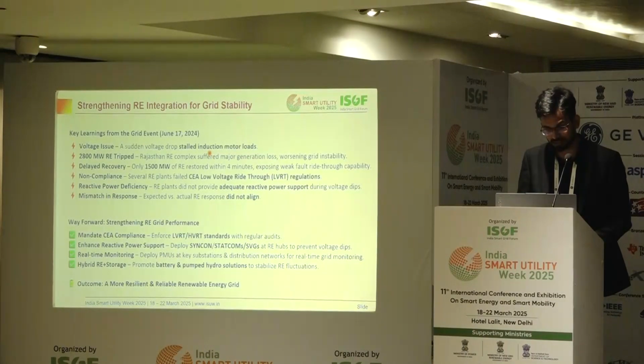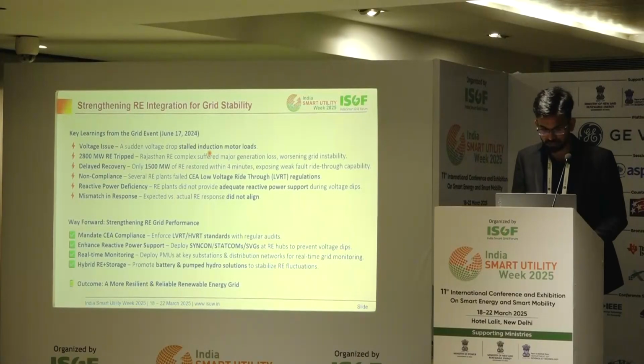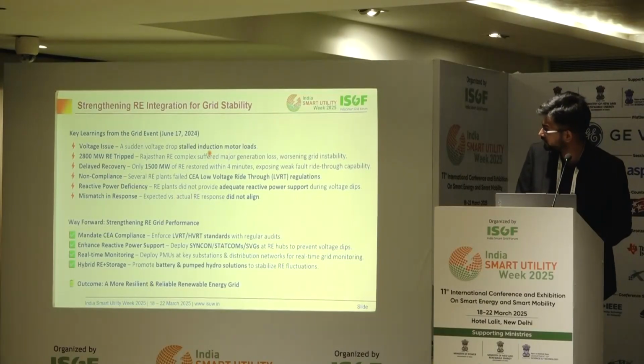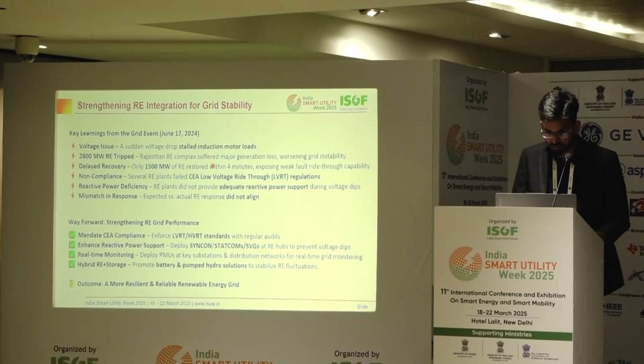So during the planning stage, instead of using a static load, we need to focus on the composite load in the system. We also observed RE tripping, as discussed earlier, because voltage was not low compared to the place where the event occurred, yet RE should not trip around 3 gigawatt. We also observed delayed recovery in many RE plants—it should recover within 1 second, but it did not. Also, the voltage ride-through capability of plants was not as per the CEA connectivity standards.